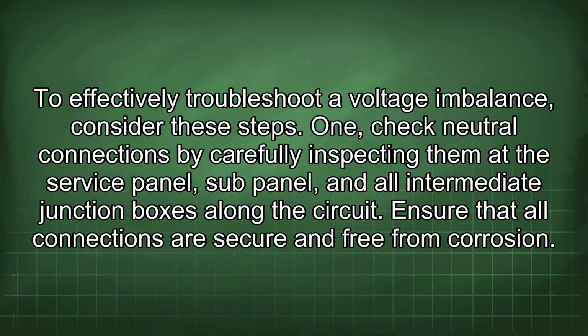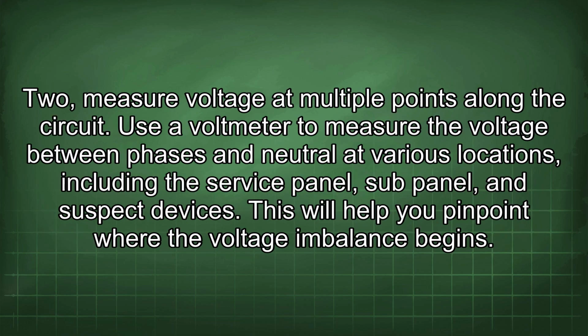To effectively troubleshoot a voltage imbalance, consider these steps. 1. Check neutral connections by carefully inspecting them at the service panel, sub-panel, and all intermediate junction boxes along the circuit. Ensure that all connections are secure and free from corrosion. 2. Measure voltage at multiple points along the circuit. Use a voltmeter to measure the voltage between phases and neutral at various locations, including the service panel, sub-panel, and suspect devices. This will help you pinpoint where the voltage imbalance begins.